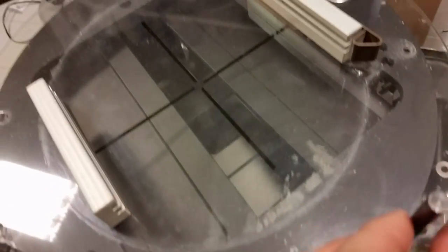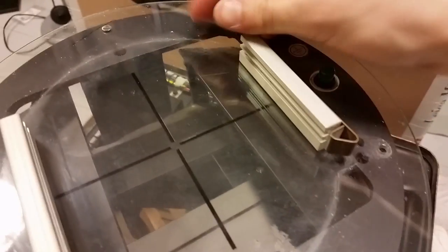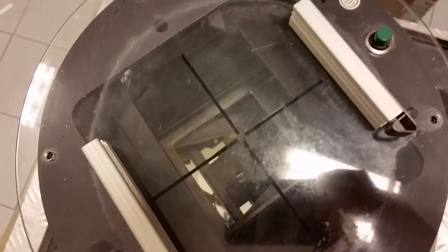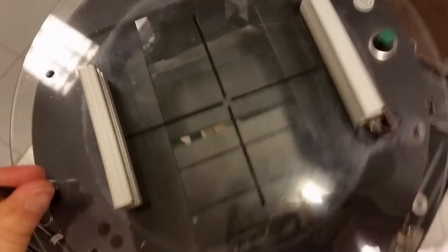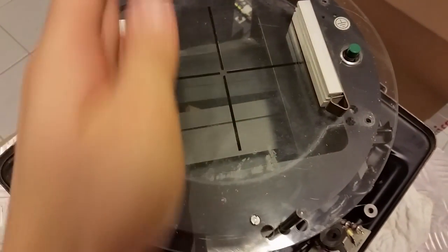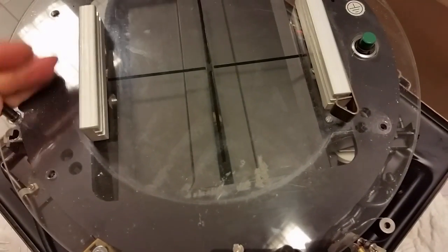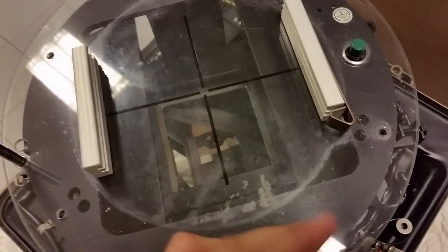And this is what actually regulates how much X-rays you want to come out. There's the one opening, and there's the other one. There's the knob, here it is. And so we've got a lot of mirrors. So now we've got a big image. And they're both open. And that's very thin. That's the X-axis, I think. So I get them right. That's the X-axis, that's the Y. Now just a little square in the middle. I'm going to open this all the way up. Get a line in the Y direction. And now you get a square.